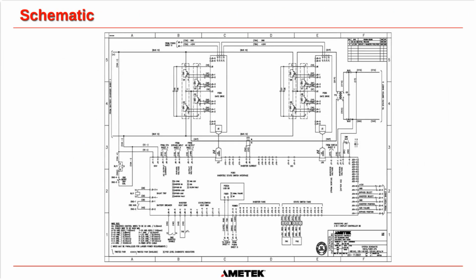And that is what an H bridge looks like inside of one of our UPSs. Once again, extremely complicated because we've got our control board down the bottom here, and there's other ancillary circuits connected here. But this at the top, this is our H bridge. Let me just show you where the H is. We've got that, and we've got that. And then the H on this one comes off here, goes through the transformer, and then it comes back on here. So that through a transformer is actually doing that. I know it's hard to see, but that is exactly what it's doing, and that's what gives you the H arrangement.